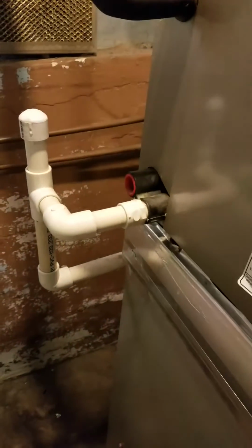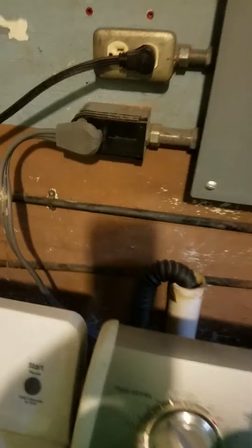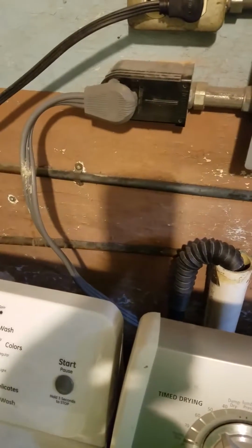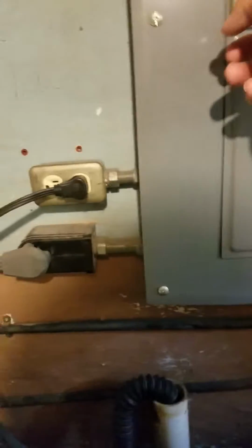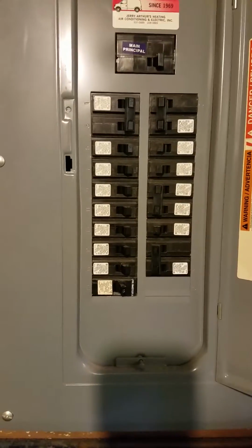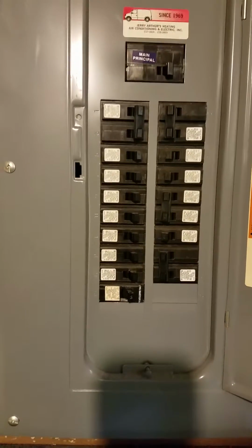So there's your drain line. We're going to need a condensate pump to go with this instead of it doing what it's doing now. So I'm going to take that off and put a condensate pump on it and run it over here to the washer drain with the tubing. Here's your electric panel, right behind this. We've got one blank in there. Currently the AC's on a double pole.